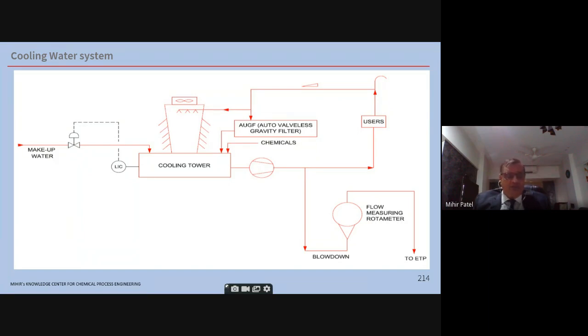This cooling tower operates by induction of air into the cooling tower using fans for the cooling. That is why a lot of dirt and dust comes into the system. So it is standard engineering practice that you have to put a filter. The AVGF operates on the return header, so it doesn't use any energy. You can also have a pressure sand filter on the discharge of the pump, and then put the pressure sand filter discharge back into the tower basin. But this uses pump power, which is higher OPEX.